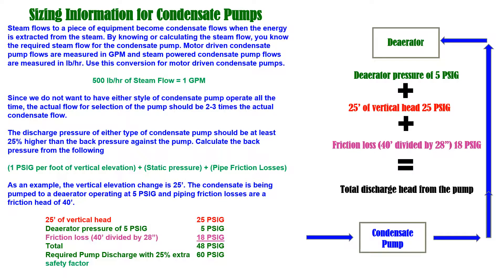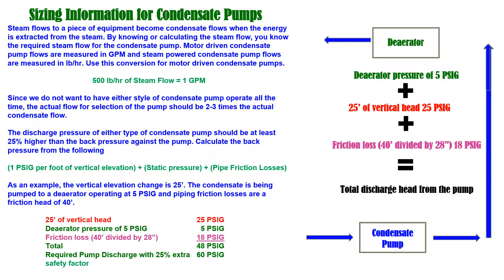The discharge pressure from a condensate pump is the sum of the vertical head, return line pressure drop, and static pressure in the deaerator. In this example, the total is 48 psig by calculation, and we suggest increasing the calculated value by a safety factor of 25%.